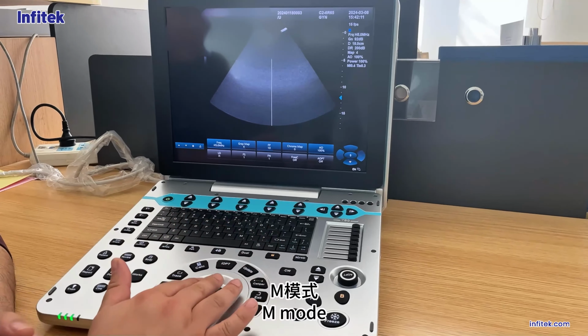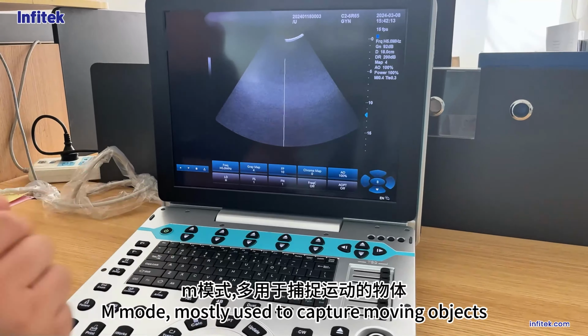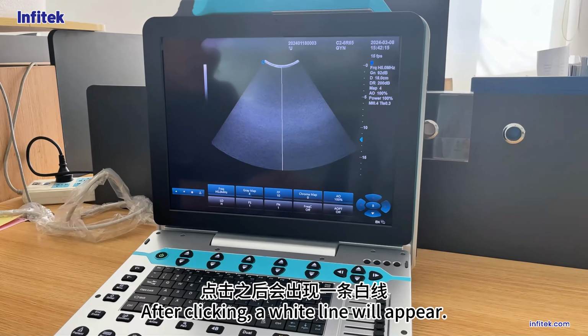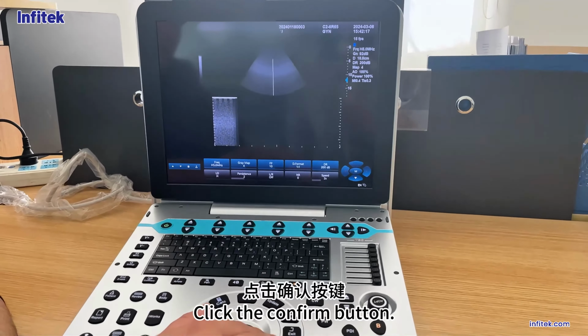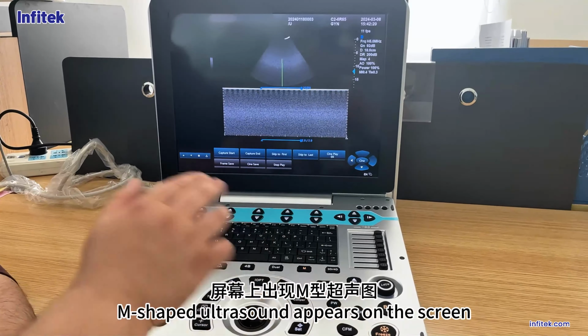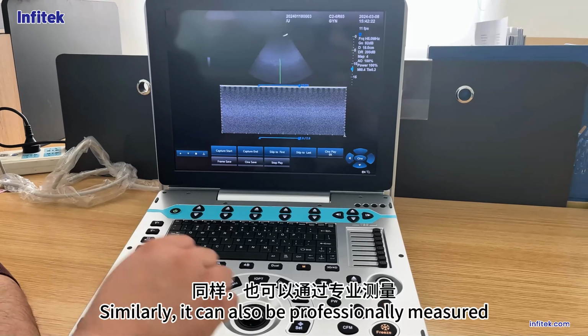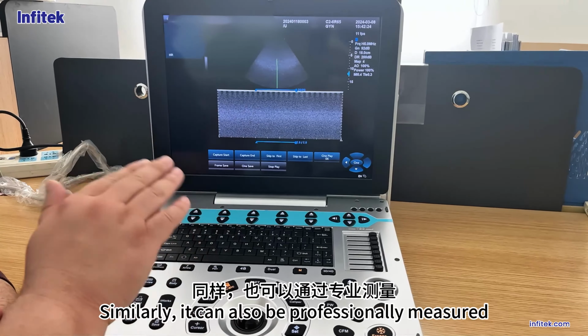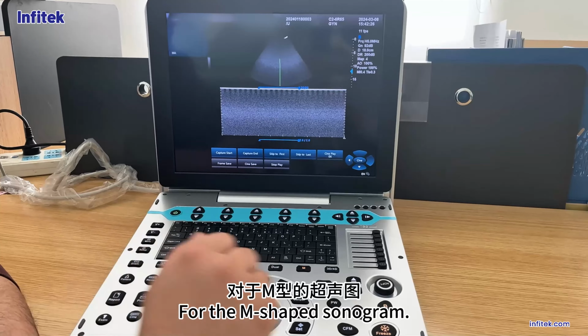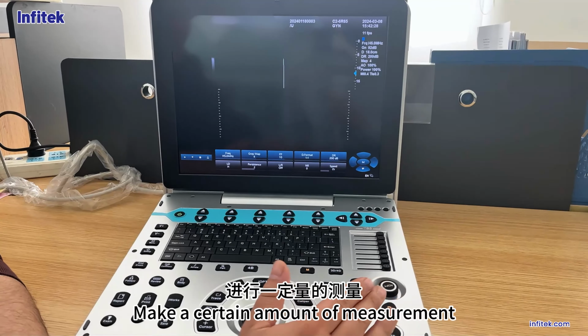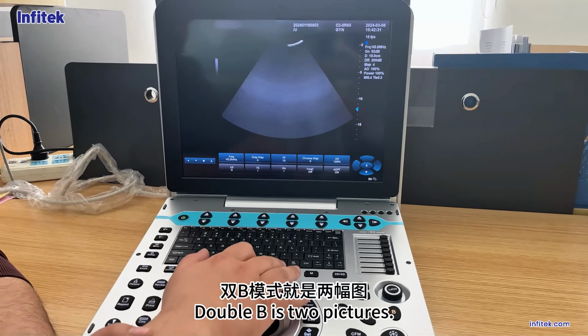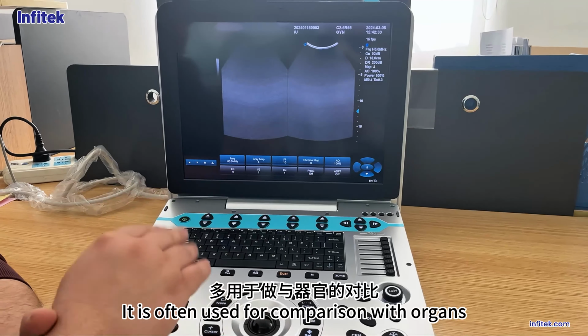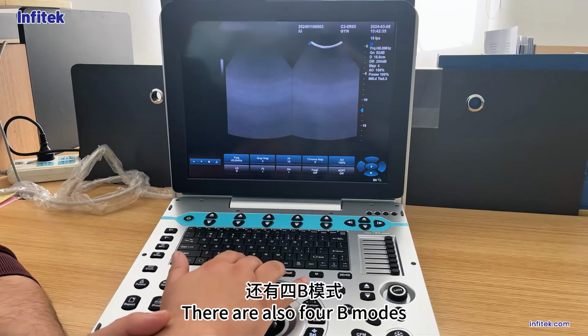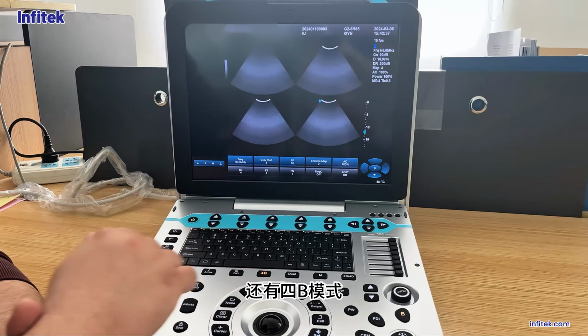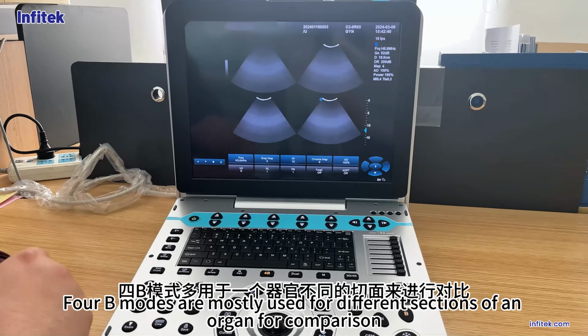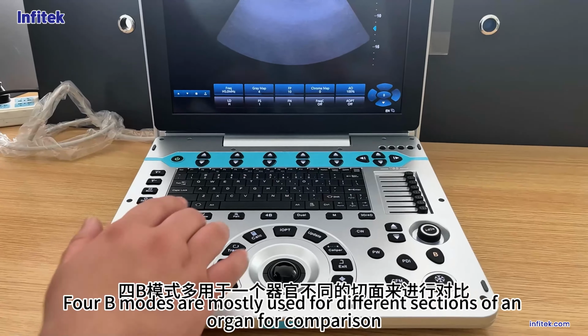M mode. M mode, mostly used to capture moving objects. After clicking, a white line will appear. Click the Confirm button. M-shaped ultrasound appears on the screen. Similarly, it can also be professionally measured. For the M-shaped sonogram, make a certain amount of measurement. Double B mode. Double B is two pictures. It is often used for comparison with organs. There are also 4B modes. 4B modes are mostly used for different sections of an organ for comparison.